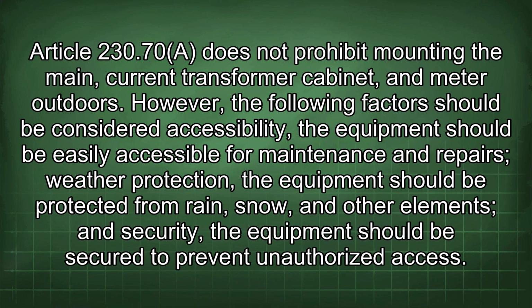Article 230.70 does not prohibit mounting the main current transformer cabinet and meter outdoors. However, the following factors should be considered: accessibility. The equipment should be easily accessible for maintenance and repairs. Weather protection. The equipment should be protected from rain, snow, and other elements. And security. Equipment should be secured to prevent unauthorized access.